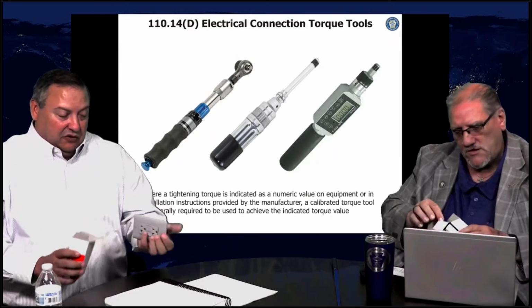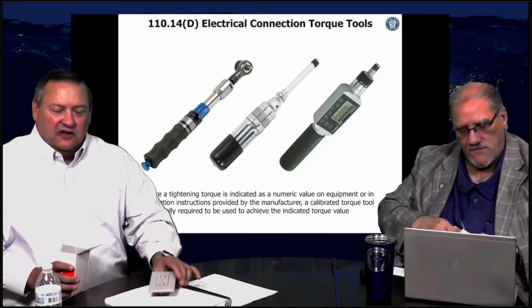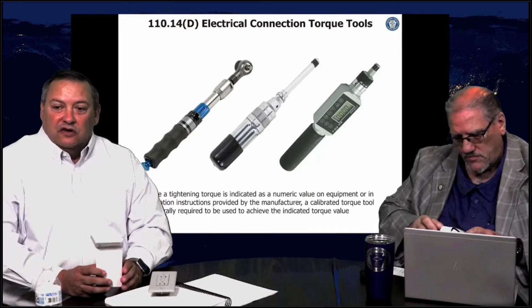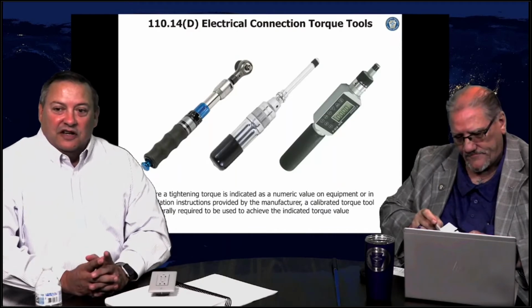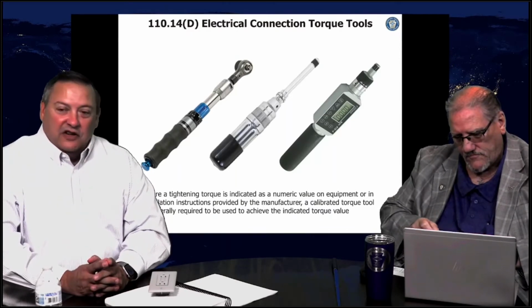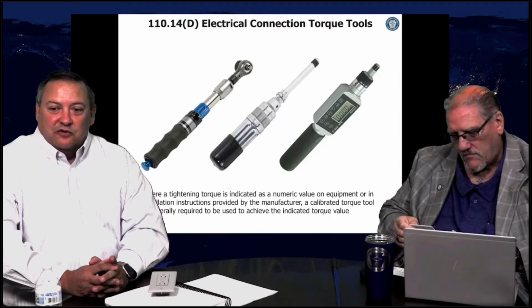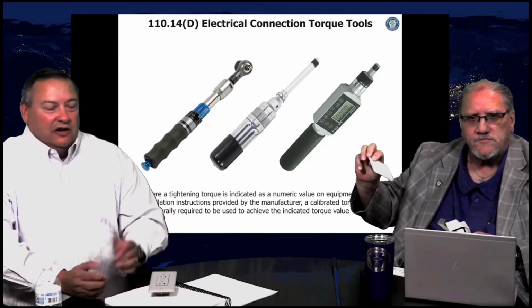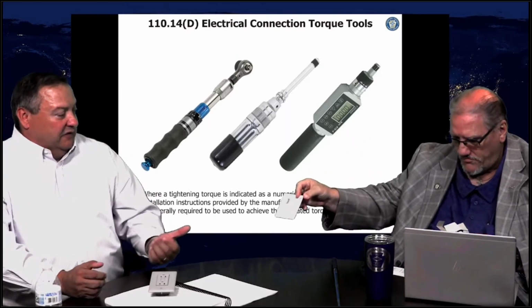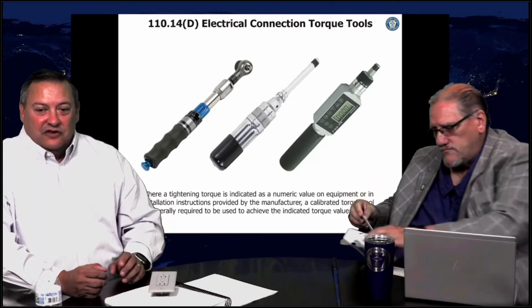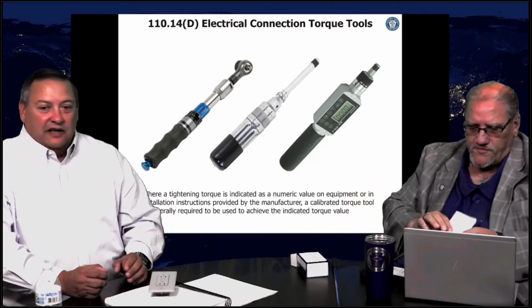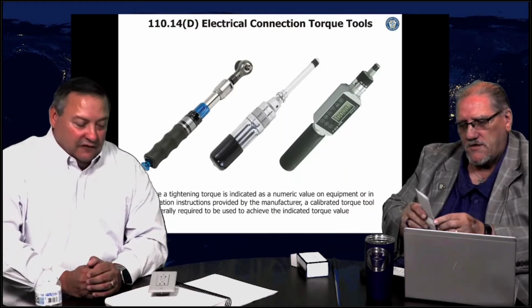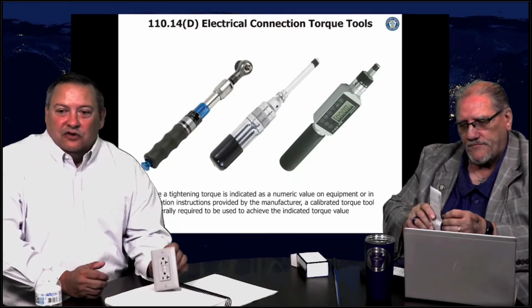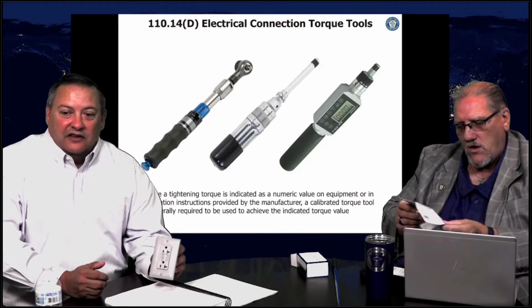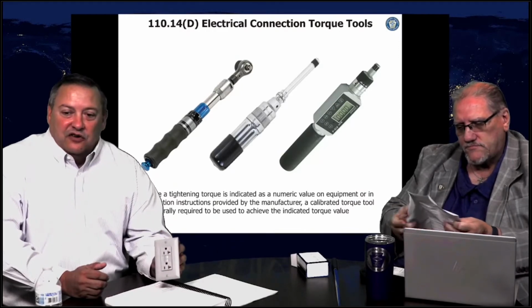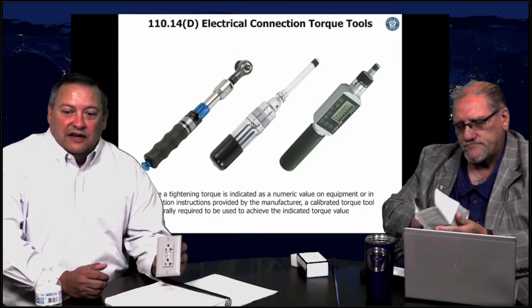They'll get this receptacle out of this box, and I've seen this so many times by electricians. The box just gets tossed. The manufacturer's information in that box is gone. And what Keith's showing you here is, as an installer, that information that comes with that device is critical to a safe installation of that device. It's going to have torquing information on it. It's going to have all sorts of information that you should read.